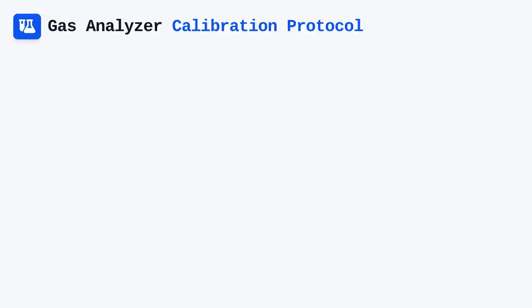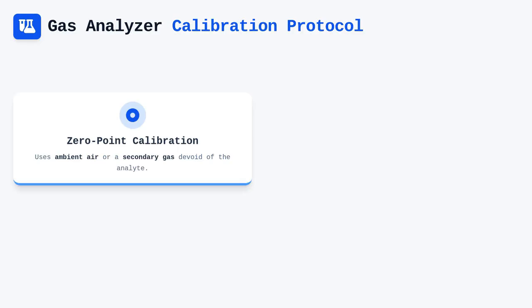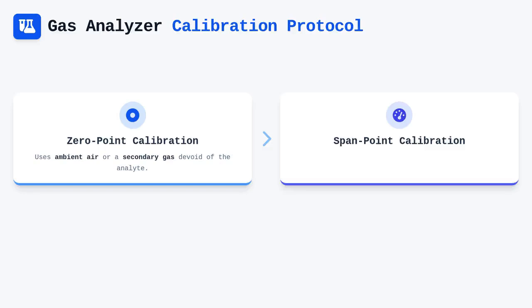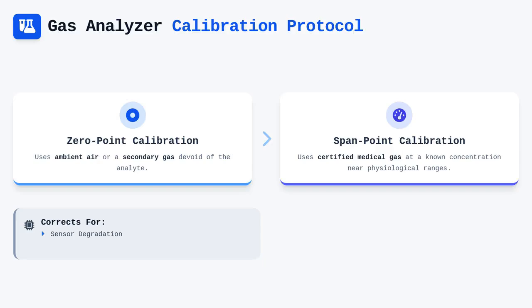Gas analyzer calibration requires an equally disciplined 2-point approach, usually utilizing a known concentration of certified medical gas. We perform a 0-point calibration using ambient air if appropriate, or a secondary gas that does not contain the analyte, followed by a span point calibration using a gas of known concentration near the expected physiological range. This process accounts for sensor degradation and potential electronic drift, which are inevitable in delicate electrochemical or infrared sensors.